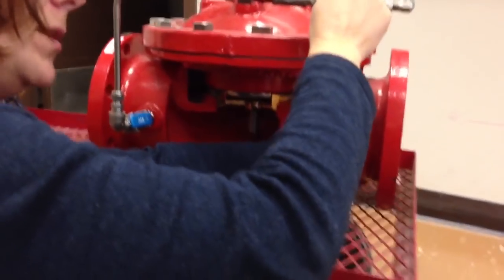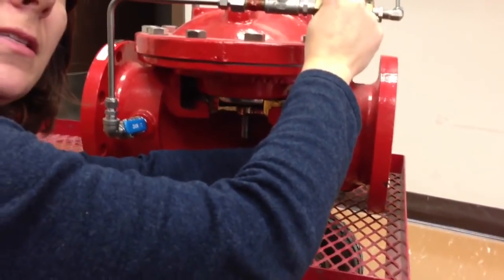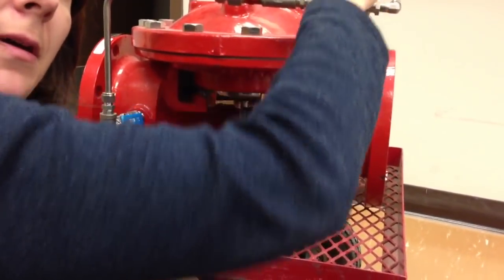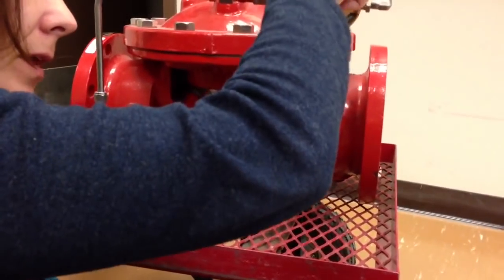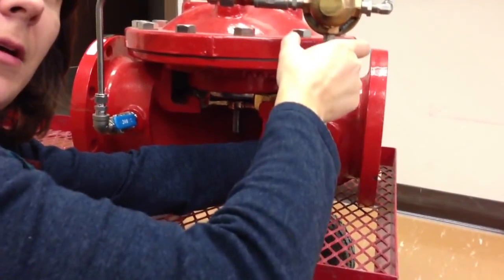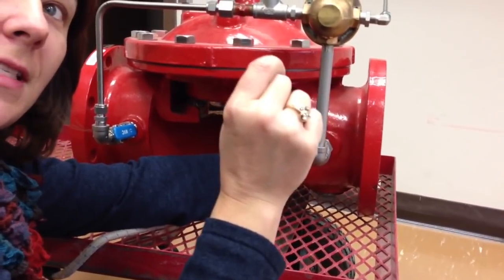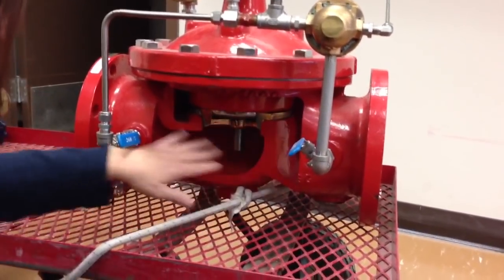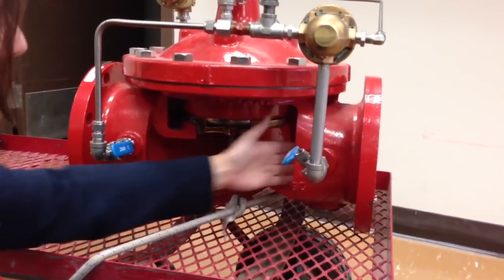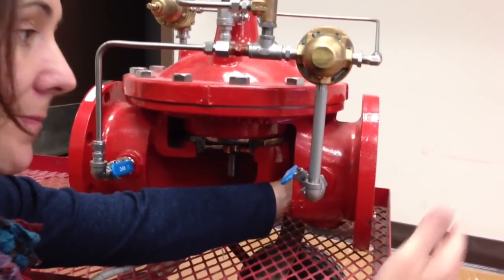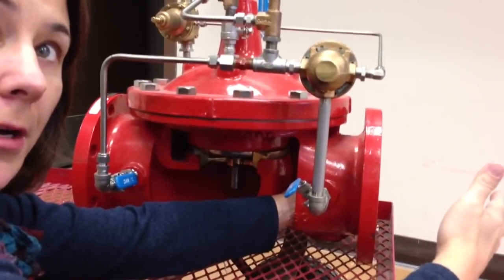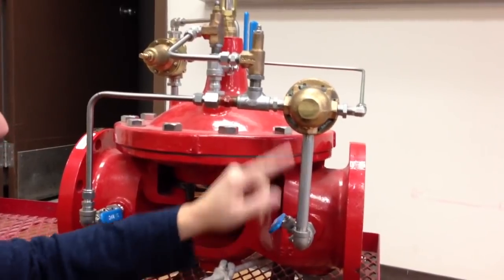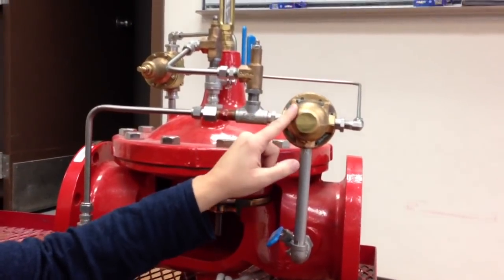So when we have a high pressure situation in here, because this is a reverse seated valve, it forces the stem to travel up, which lifts the saddle assembly up, which brings the disc closer to the seat, which closes the valve. If this pressure rises too high, and that will happen when your downstream users stop using water, this pressure will build in here. That high pressure will be transmitted in here, and then this valve will start to close.